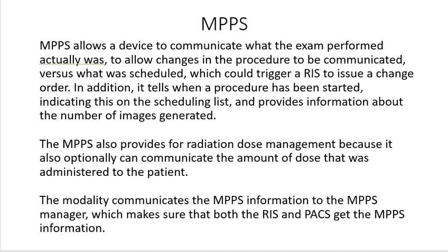MPPS allows the device to communicate what exam was performed, to allow changes in the procedure to be communicated versus what was scheduled, which could trigger a RIS to issue a change order. In addition, it tells when a procedure has been started, indicating this on the scheduling list, and provides information about the number of images generated.